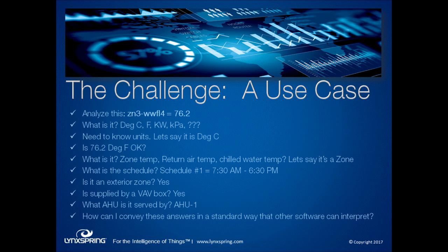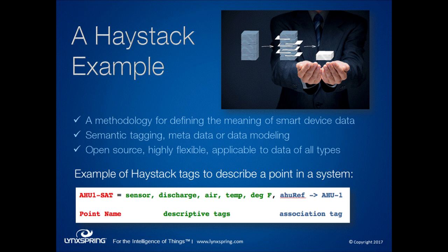Let's say it's a zone temperature. I need to know more before I can comment on whether that value is okay — what's the schedule? 76.2 on night setback might be fine. I might also want to know if it's an exterior zone, if it's a VAV type system, what air handler serves it — because if it's warm there, the problem might be with the air handler. So what we want to address is: how do we convey answers in a standardized way that's both human readable and machine readable? A simple Haystack example uses semantic tagging — people also call it metadata or data model — to describe the meaning of data.